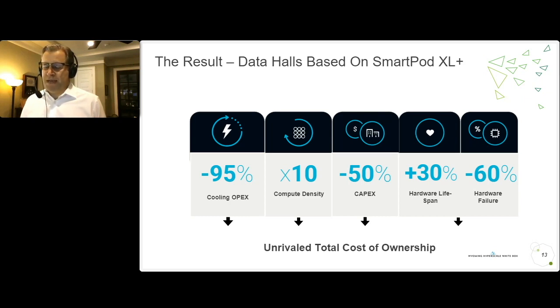We get about 10 times more dense compute within the data center halls, actually more than that. Our CapEx goes down by half based on the savings of space. The last two figures are only calculated on about 3 years of runtime, since those are the oldest deployments we have in warranted ITE for liquid cooling. We think hardware lifespan and failure rates will actually be better than what we're showing here once we run them for longer.